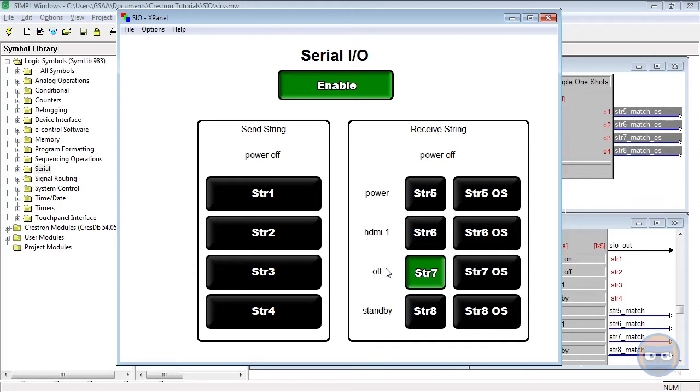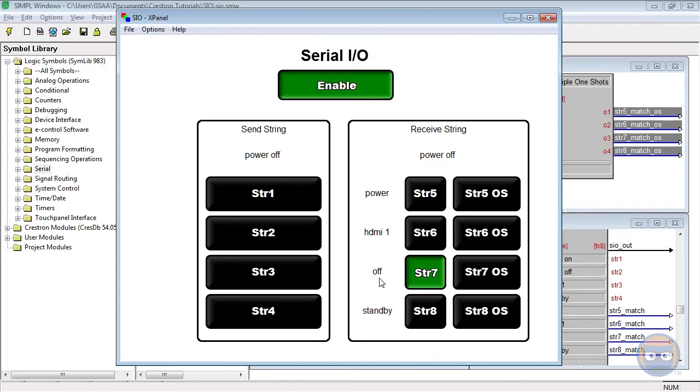So there are a couple things we can take away from this. Number one is a digital output on the S.I.O. will stay high if the last characters of the received string match the string parameter completely. And the second one is that a digital output on the S.I.O. will go high temporarily if the string parameter is contained somewhere inside of the received string.